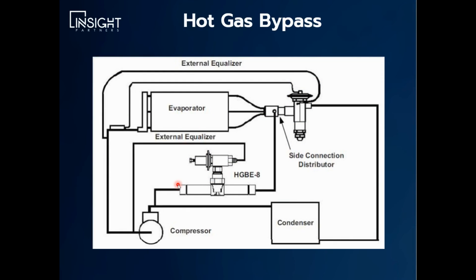Hot gas bypass is a totally different strategy, totally different animal. You have your four basic components: your compressor, condenser, TXV, and an evaporator. What happens in some HVAC systems is you have a varying load condition — it could be pretty dramatic, like a VAV application or a 100% outdoor air application. If this is a five-ton compressor and you have five tons of load, that's great. But let's say your load drops to two tons. What happens is the refrigerant starts to get very low in temperature and pressure as it gets sucked back into the compressor — it actually freezes up your system.